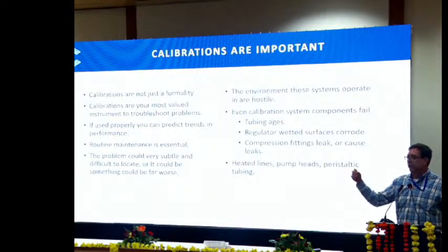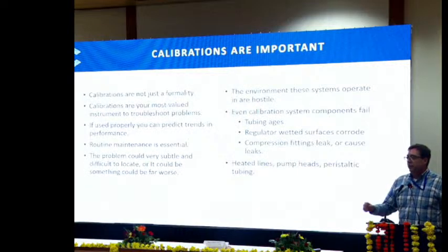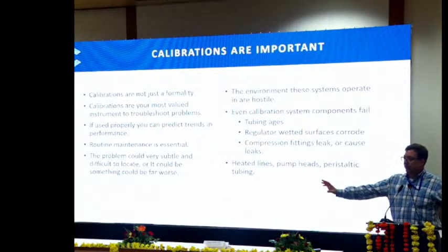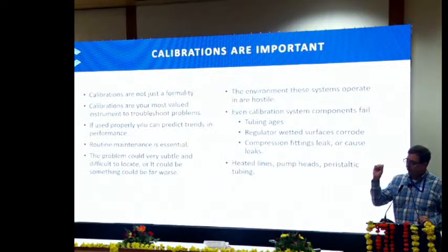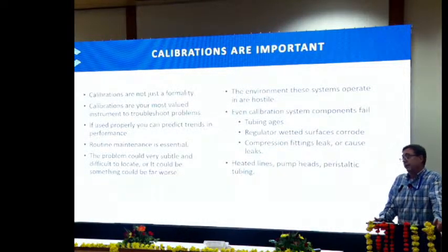You look down the probe, you're looking at everything, and you think, everything's fine, I don't know where the leak is coming from. You pull the internal sheath out, and you look at it very closely, and you can have a pinprick of a hole in there, and that will ruin your day and your data. So do not underestimate a calibration.